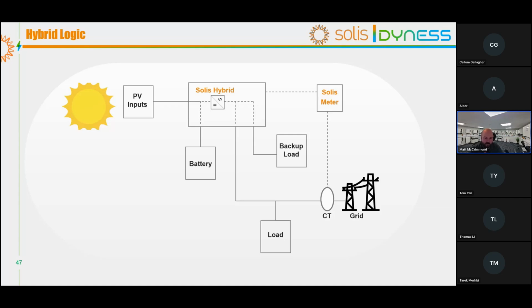that the grid, we're pulling energy from the grid, then the hybrid inverter will know in order to discharge that energy back onto the grid port, because its job is to keep that CT reading 0 as much as possible. What does happen is, because it's dynamic and there's signals getting sent between the CT to the inverter, it's calculating that, and then the load is also fluctuating.